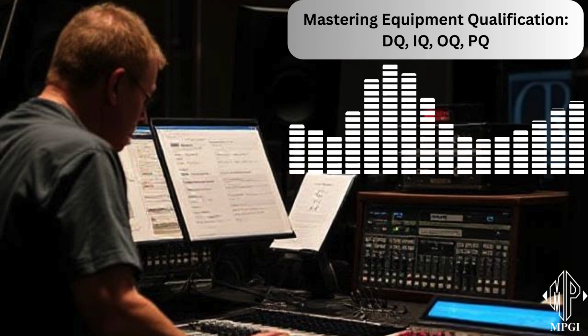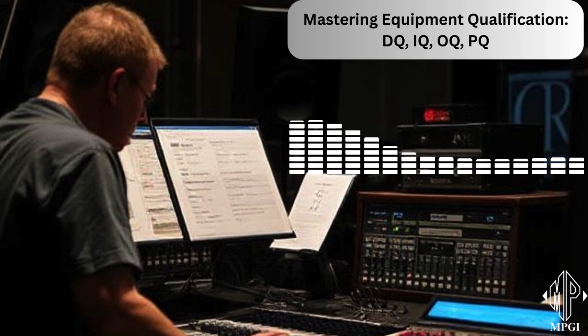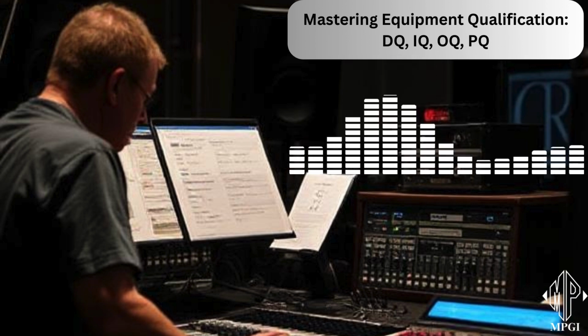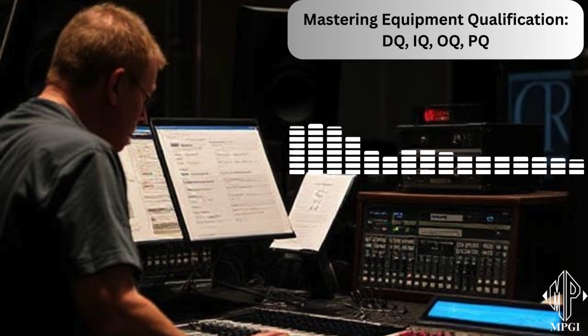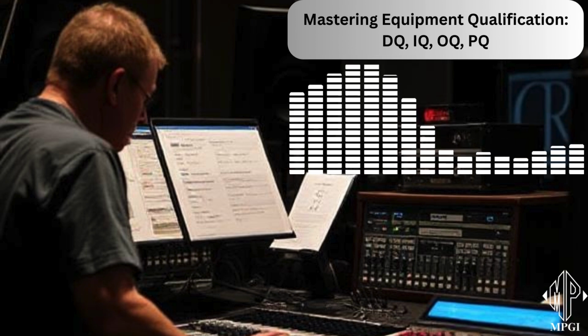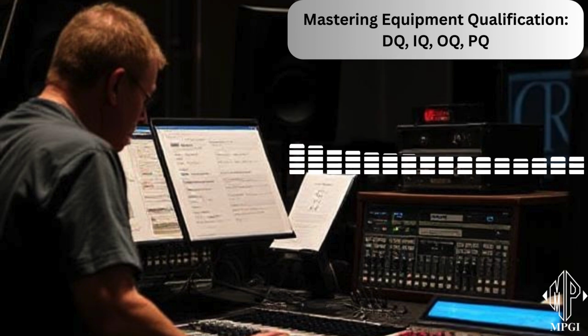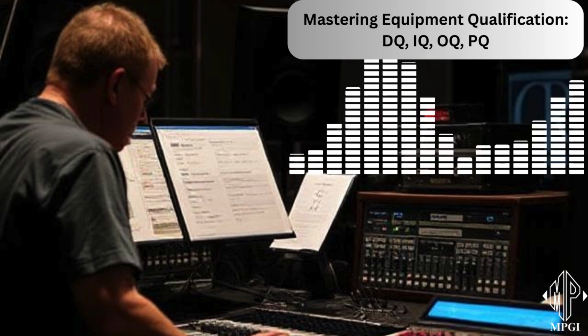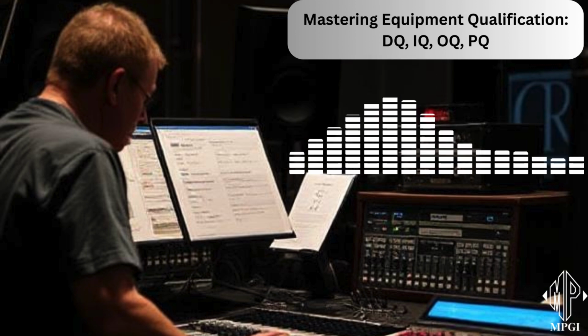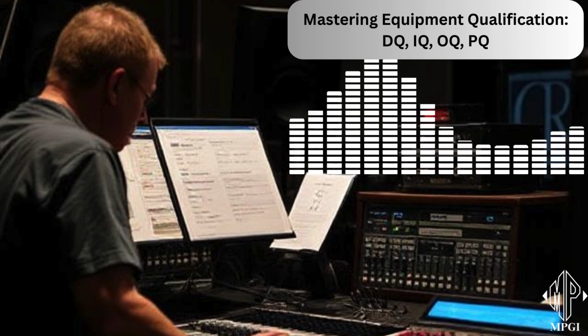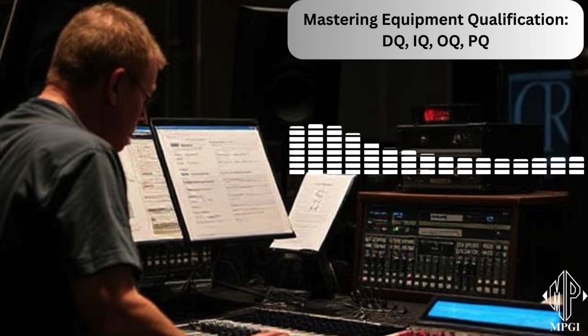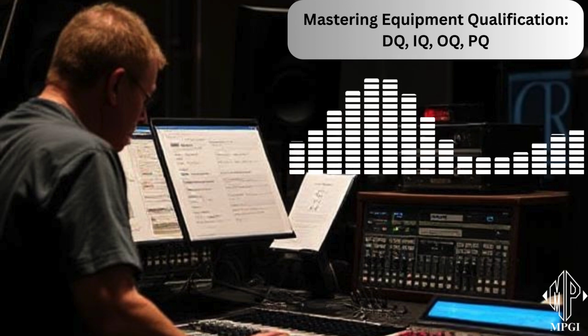Right. And then they create a detailed IQ protocol, a step-by-step guide for the entire process, outlining all the tests, inspections, acceptance criteria, and what documentation to keep. It sounds incredibly thorough. Oh, it is. And then qualified personnel execute that protocol. They do all the tests, make sure everything's installed correctly, verify calibrations of any instruments used during installation, and ensure the control systems are working as they should.